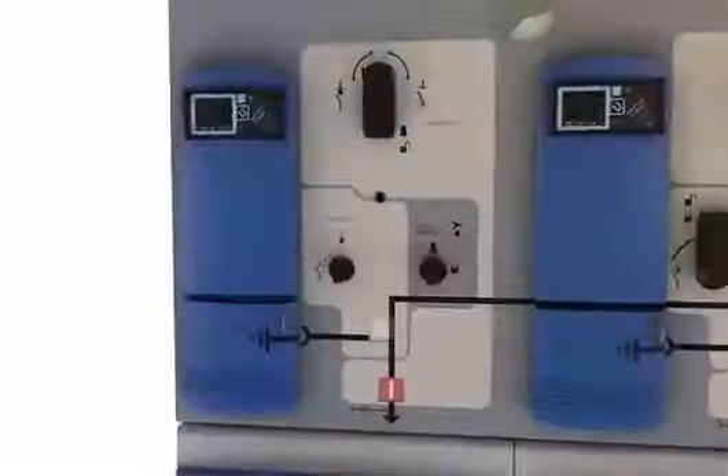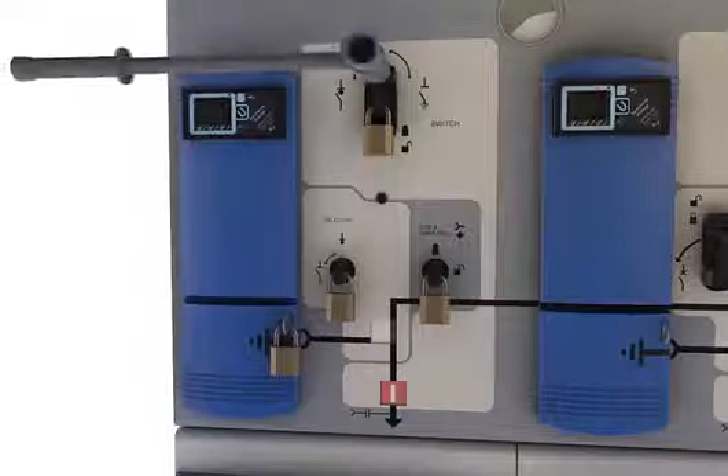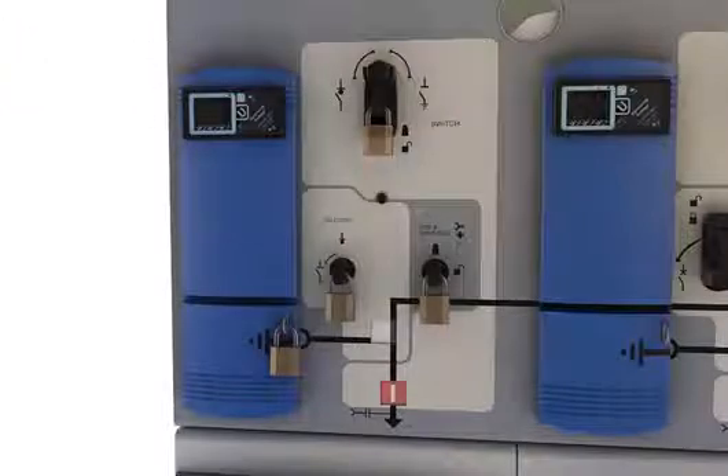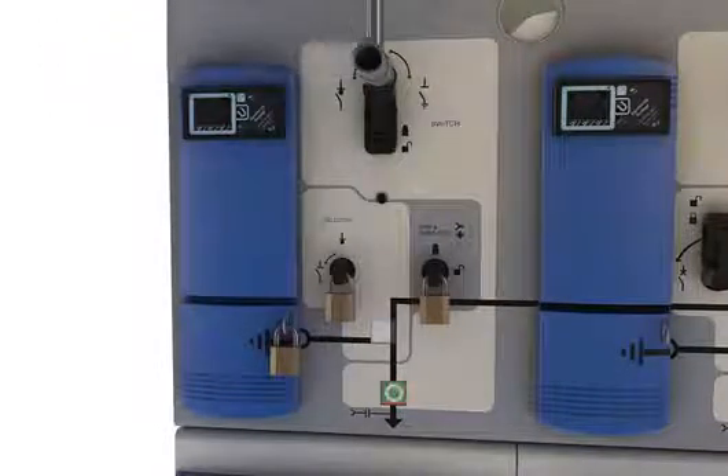All operating mechanisms are fully interlocked with padlocking facility to prevent unintended or unauthorised operation. The load break switch mechanism is equipped with an anti-reflex mechanism to prevent immediate reverse operation of the switch, providing maximum safety to the operator.